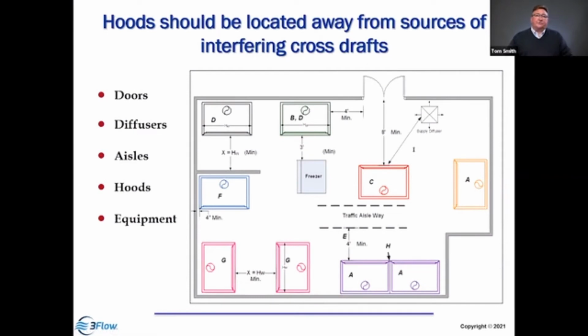So that led us to some identification of some recommendations for hood location. We want them to be at least 5 feet away from a supply diffuser. We want hoods to be 4 feet from traffic aisles. We want to be at least 3 feet away from major obstructions like refrigerators or freezers. And 2 hoods facing one another should have the distance, the width of the hood, between them. So if you have a 5-foot hood, it should have 5 feet between them. If you have 6-foot hoods, it should be 6 feet. And that has to do with the hoods stealing air from one another. So if they're too close, they'll compete for airflow and can be a problem.